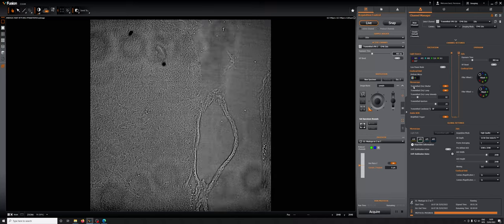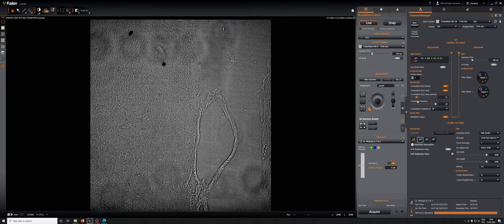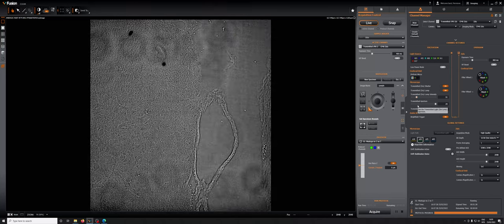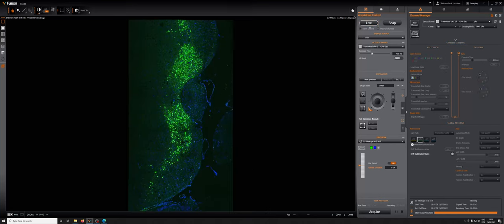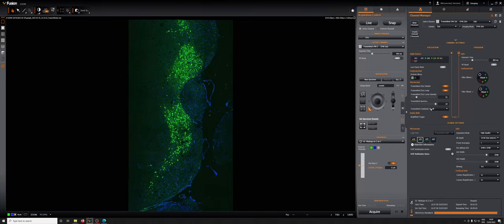Let's say we're happy with what we've done here. The other thing that's critical for being able to use a transmitted light channel in combination with the fluorescence ones is once we've set up the transmitted light channel we have to go to each of the fluorescence channels and turn on the shutter and the lamp.